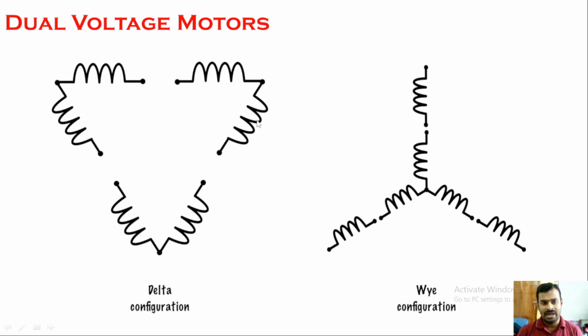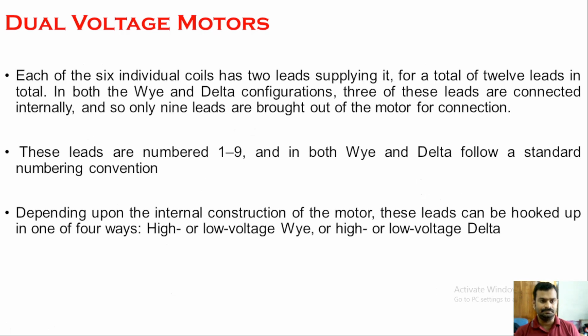In case you have a motor and you don't know the nameplate details and you don't know how to identify whether it is a star connection motor or a delta connection motor, I am going to show you how you can check the motor terminals to find out whether it is a star connected motor or a delta connected motor. These motors will usually have either 9 terminals or 9 wires coming out of the motor, or it may have 12 wires coming out of the motor. Two different configurations are available.